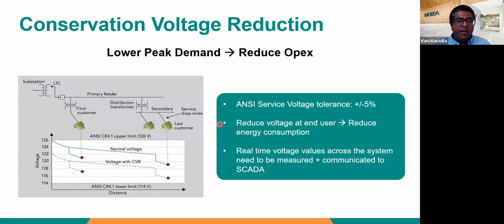One of the schemes used by utilities is what you call CVR. Going back to our initial challenges about reducing peak demand, this is a scheme which looks at voltages across the system and tries to optimize the voltage at the last point in order to manage the amount of power that needs to be sent.